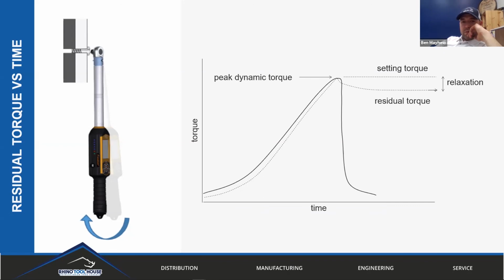So kind of what you were saying, Kyle: the foundational assumption has to be that the inline rotary is good. We get that question from ISO all the time, though, and the way you have to think about it, your master needs to be calibrated at an interval. You want to make sure you're well within calibration, calibrated by someone who is ISO 17025, like us, who knows what they're doing.